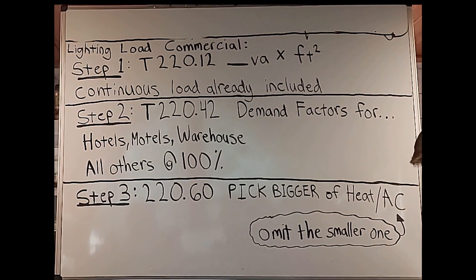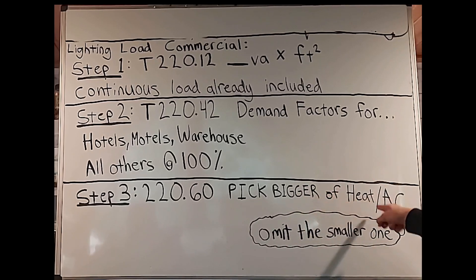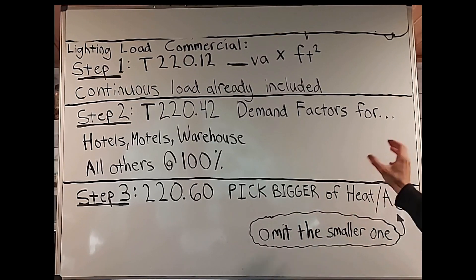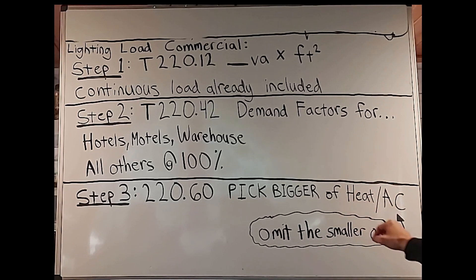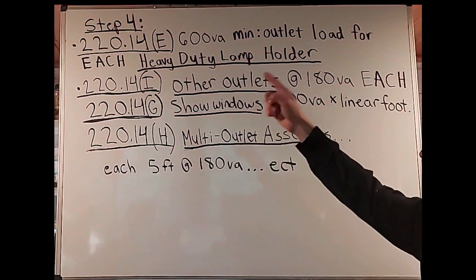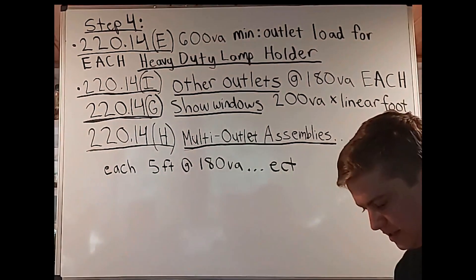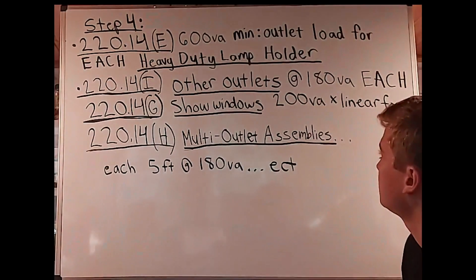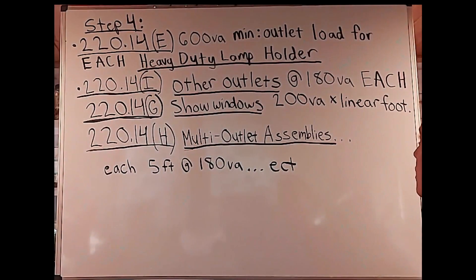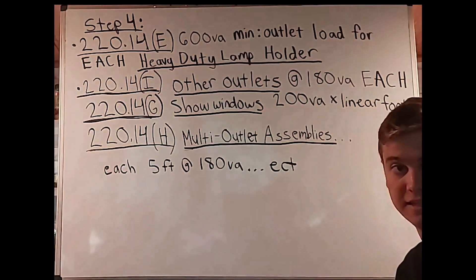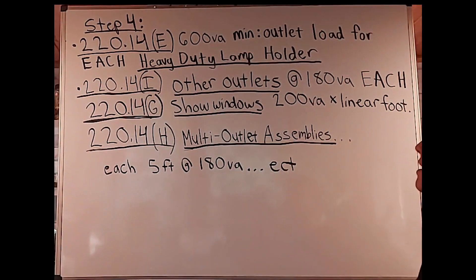Next is step four. We go back to article 220.14, subsection E — heavy-duty lamp holders. It tells us there's a 600 volt amp minimum for the outlet load for each heavy-duty lamp holder. That's the minimum, so if you're told it's more, you use that higher number. Then subsection I covers other outlets. Except for subsections J and K — J being dwelling units and K being office buildings — all other outlets are rated at 180 volt amps each as a minimum.